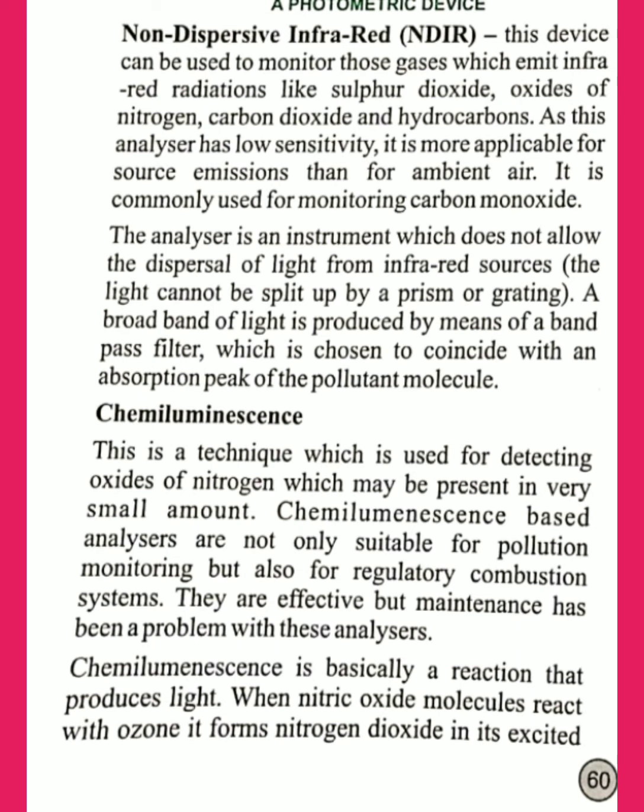Next is chemiluminescence, which is basically a reaction that produces light. This technique is used for detecting oxides of nitrogen, which may be present in very small amounts. When nitric oxide molecules react with ozone, it forms nitrogen dioxide in its excited state. A small fraction of these molecules decay by emitting photons when mixed with ozone, and light is given off. The amount of light emitted gives a measure of the concentration of nitric oxide present in the sample.